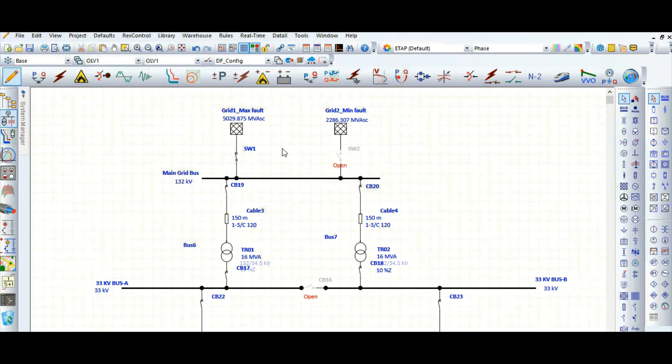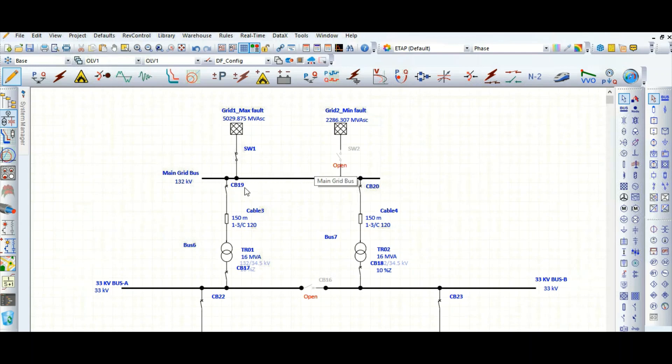With the help of load flow study case editor, this is the system I have drawn. There is a grid connected with the main 132 kV receiving substation. From there, two step-down transformers are stepping down the voltage at 33 kV level, and further downstream network is there at 6.6 kV and 415 volt, 690 volt.